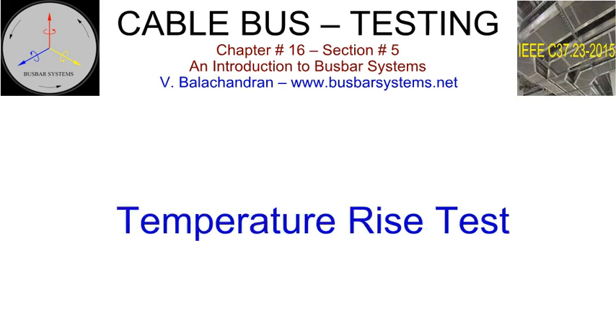Temperature rise test. The length of the test piece and extension of the conductor on either end shall be similar to that specified in IEEE 37.23 year 2015. The temperature sensing device shall be embedded in the cable on the surface of the conductor. Most of the cables are rated for continuous operation at 75 degrees Celsius or 90 degrees Celsius. This corresponds to a maximum temperature rise of 35 degrees Celsius or 50 degrees Celsius over an ambient of 40 degrees Celsius. The temperature withstand capability depends upon the class of insulation of the cable. The results of the temperature rise tests can be interpolated for other ambient temperature and temperature rise for similar interphase and intraphase configuration and matrix of cables by adopting the method suggested by Neher-McGrath.